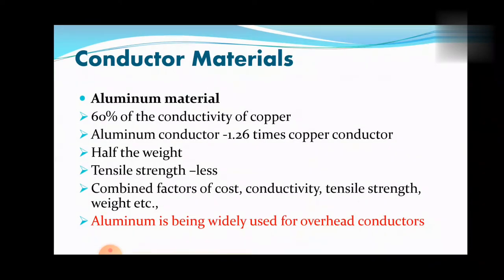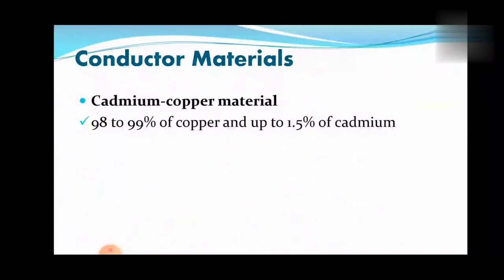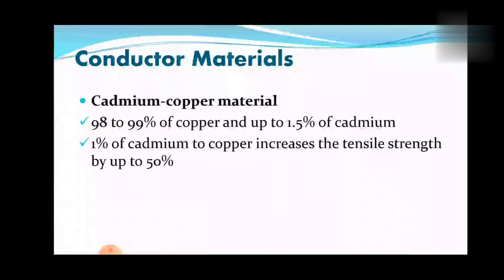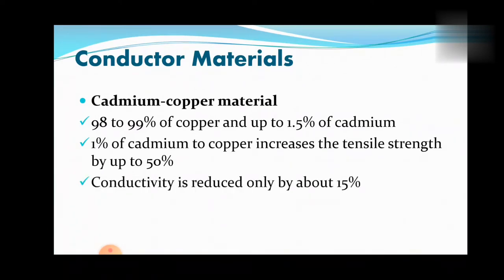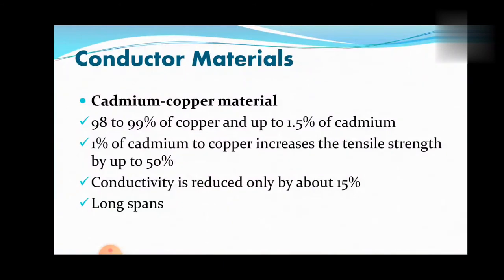Regarding cadmium copper material, cadmium copper alloys contain approximately 98-99% of copper and up to 1.5% of cadmium. Addition of about 1% of cadmium to copper increases the tensile strength by up to 50%, and the conductivity is reduced only by about 15%. Therefore, cadmium copper conductors can be useful for exceptionally long spans. However, due to the high cost of cadmium, such conductors may be uneconomical in many cases.